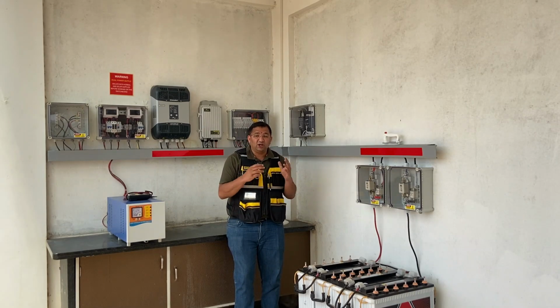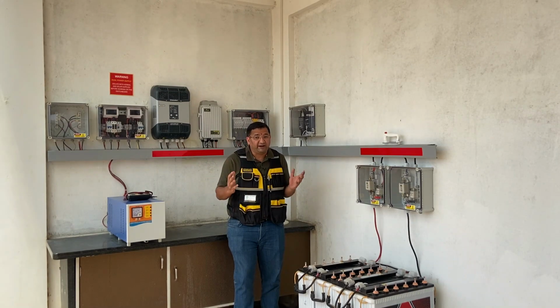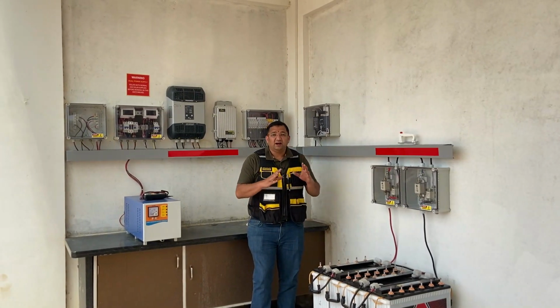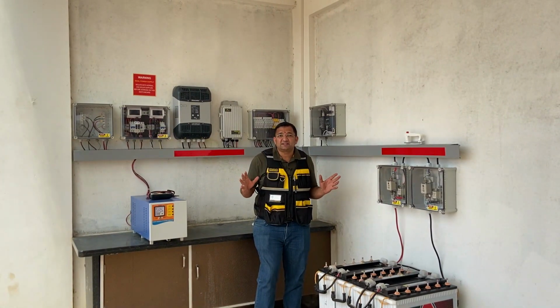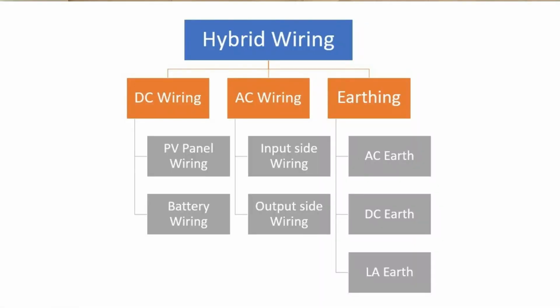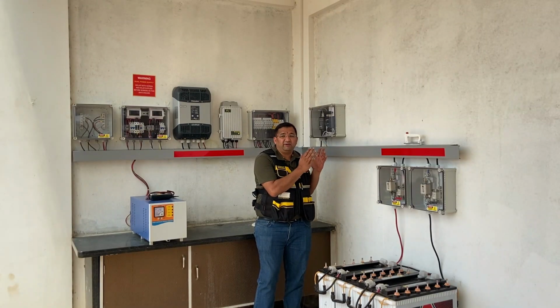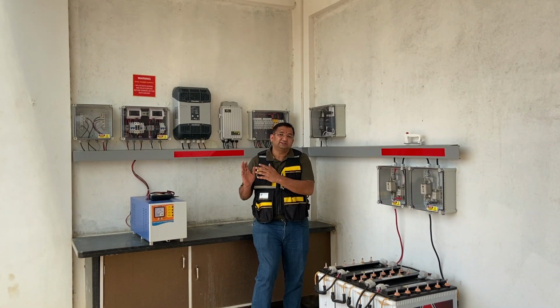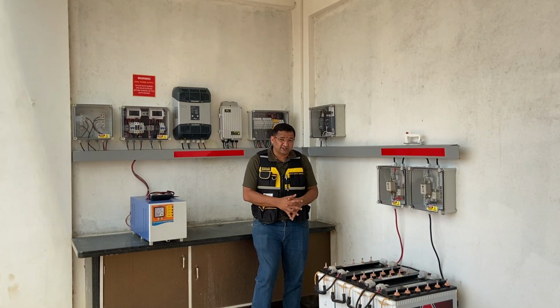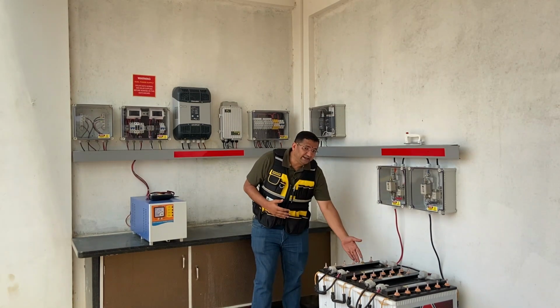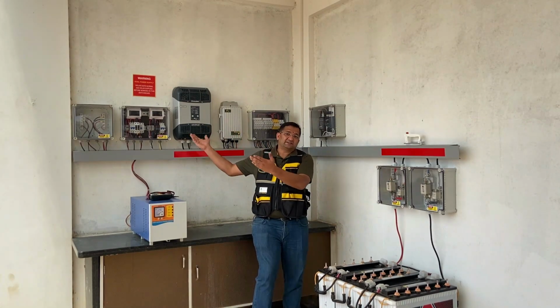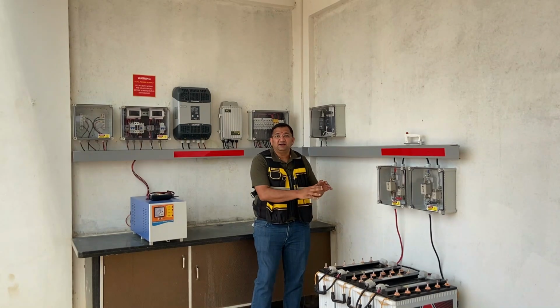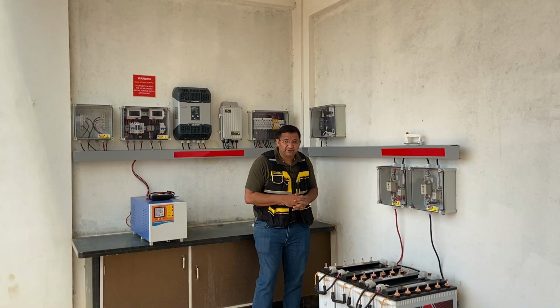Now we will discuss part by part about the wiring of this system. Broadly we can categorize the wiring into 3 components: the DC wiring, the AC wiring, and the earthing. For the DC wiring, we have the wiring from the panel to the array junction box, from the array junction box to the charge controller, and from the battery to the charge controller as well as the inverter. This forms the DC part of the wiring.